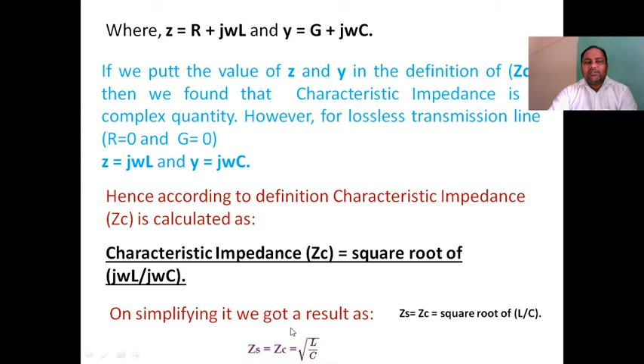Normally, the value of ZC in overhead transmission lines varies between 400 to 600 ohms, while in underground cables it is much less, varying between 40 ohms to 60 ohms. So finally, the characteristic impedance ZC is equal to root L by C, where L is the inductance of the transmission line and C is the capacitance of the transmission line.